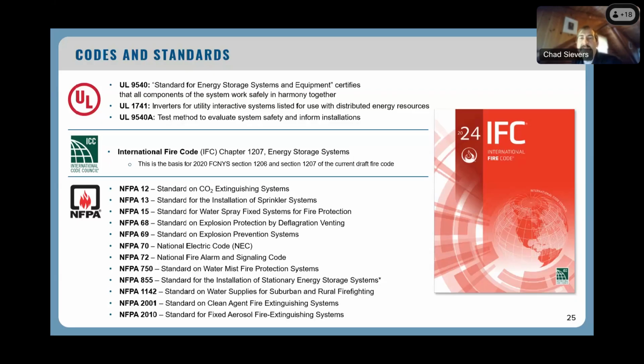The UL standards provide important product testing and certification updates for products, as Bill mentioned. The NFPA standards are typically geared towards installation requirements and hazard reduction, with NFPA 855 focusing on ESS technology specifically. Tying it all together is the International Fire Code, which provides model language for the Fire Code of New York State, consolidating all the standards and providing additional requirements.